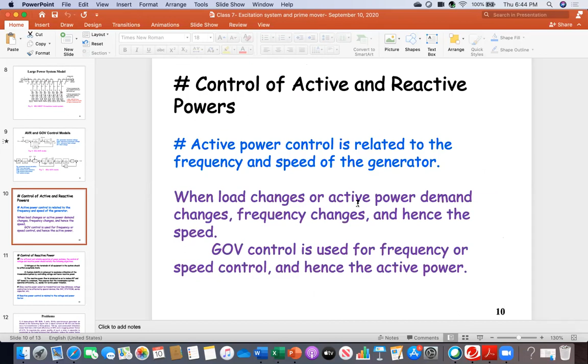All are interrelated, but still there is some difference. It depends on the mode of dominance, which depends on the system structure. For example, if a system has an induction machine, or more wind generators than synchronous machines, then your dominating mode will be reactive power control, and hence controlling voltage and power factor. If your system has a synchronous machine, your main goal will be to control active power, frequency, and speed. So typically, if you have a synchronous machine, you give preference to active power, frequency, and speed. If you have an induction machine, you give priority to controlling reactive power, voltage, and power factor. All are interrelated.